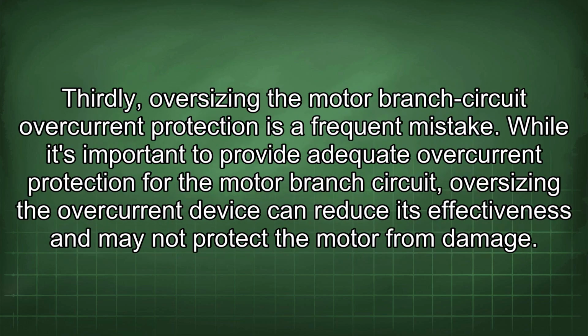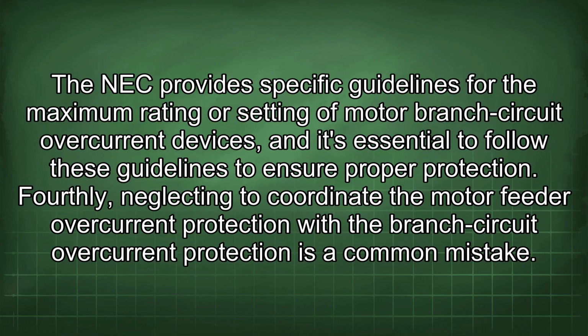Thirdly, oversizing the motor branch circuit overcurrent protection is a frequent mistake. While it's important to provide adequate overcurrent protection for the motor branch circuit, oversizing the overcurrent device can reduce its effectiveness and may not protect the motor from damage. The NEC provides specific guidelines for the maximum rating or setting of motor branch circuit overcurrent devices, and it's essential to follow these guidelines to ensure proper protection.